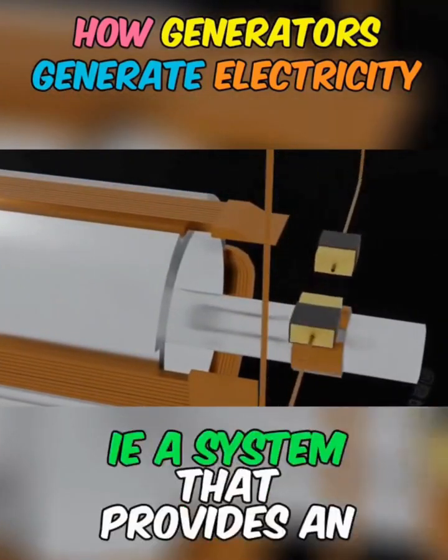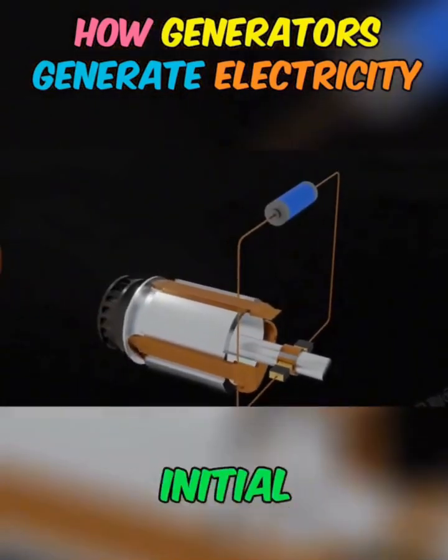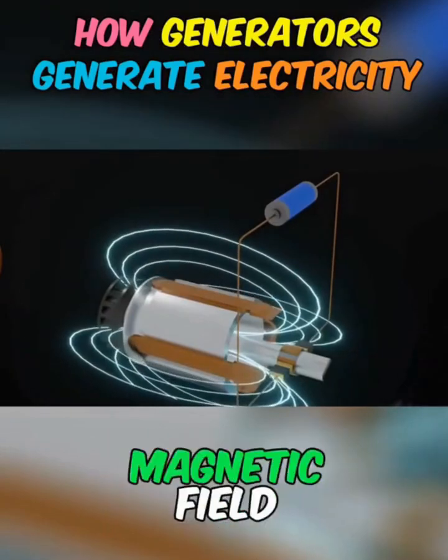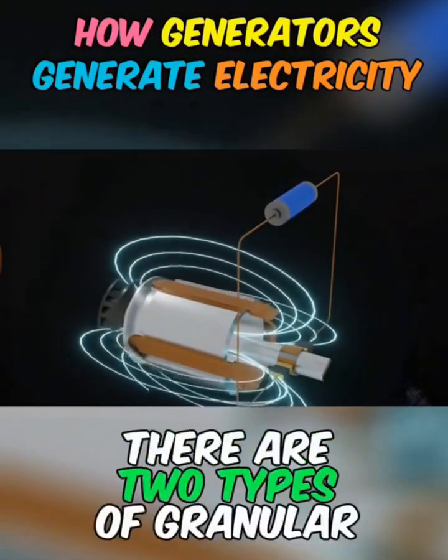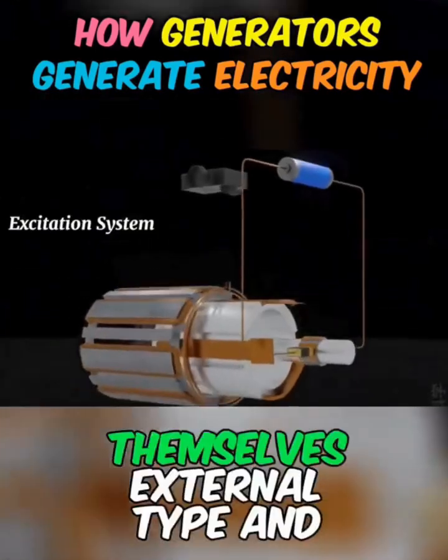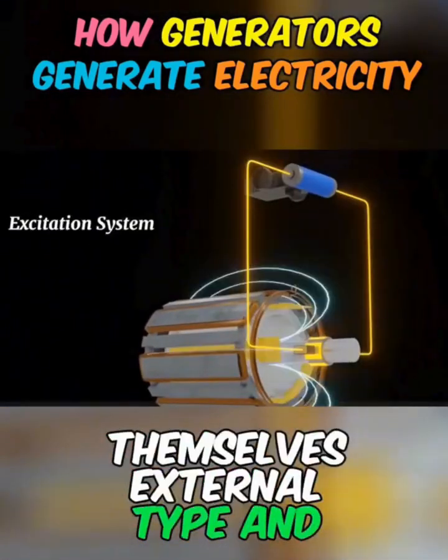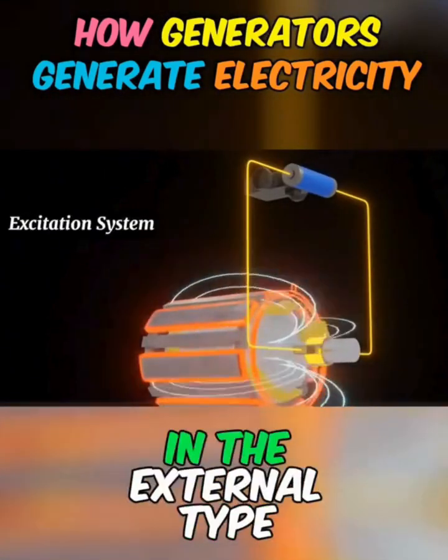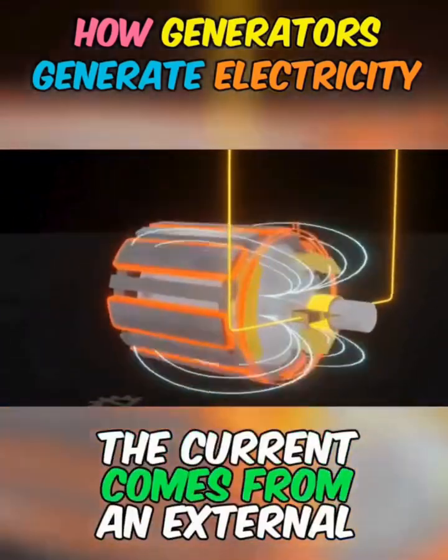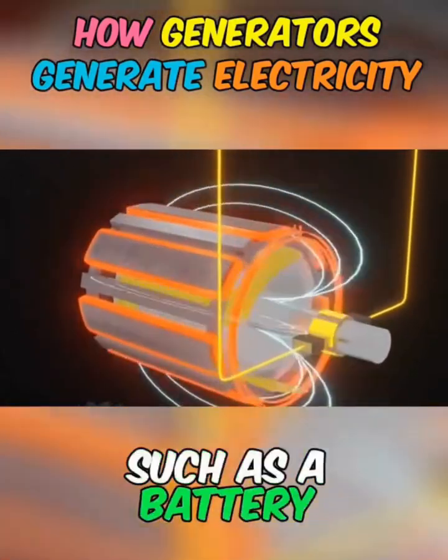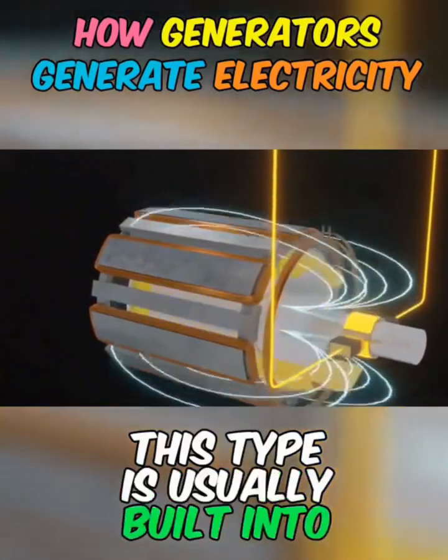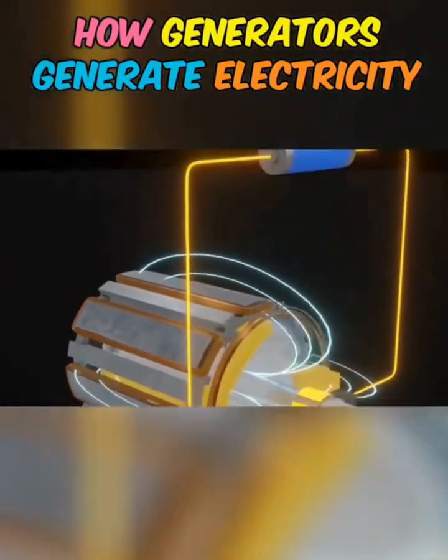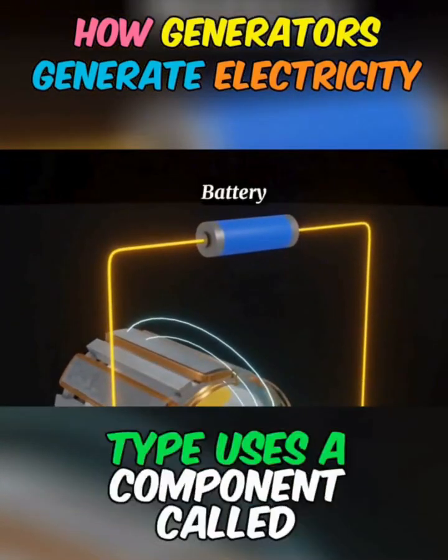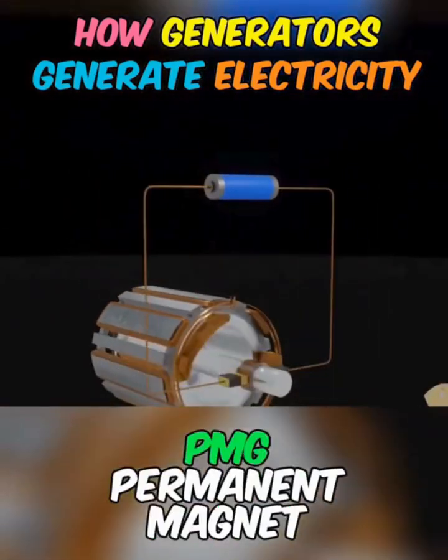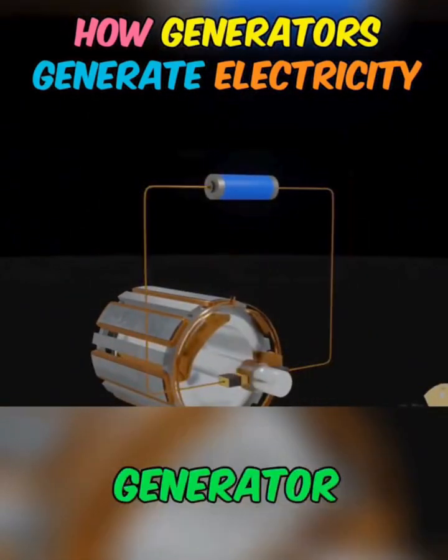This is called an excitation system, i.e., a system that provides an initial current to generate a rotor magnetic field. There are two types of excitation systems themselves: external type and self-generated type. In the external type, the current comes from an external source such as a battery. This type is usually built into the alternator on the car. While the self-generated type uses a component called PMG, permanent magnet generator.